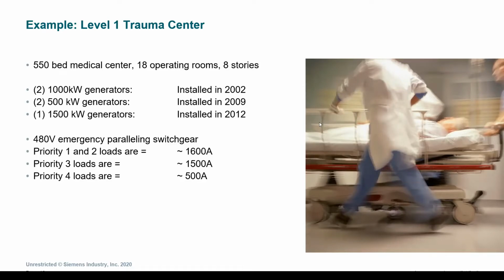During the evaluation stage, the emergency paralleling switchgear has the loads defined as such. Priority 1 and 2 loads are a combined 1600 amps, and priority 3 loads is a combined 1500 amps, followed by the priority 4 or the optional standby load of 500 amps. Hopefully many of you have already identified that the capacity or the load for priority 1 and 2 exceed the amp rating for 2 of the generators listed.